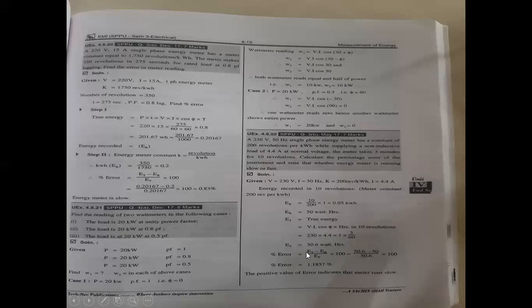Percentage error = (true energy − recorded energy) / true energy × 100 = (50.6 − 50) / 50.6 × 100 = 1.185%. The positive value of error indicates that the meter runs slowly.